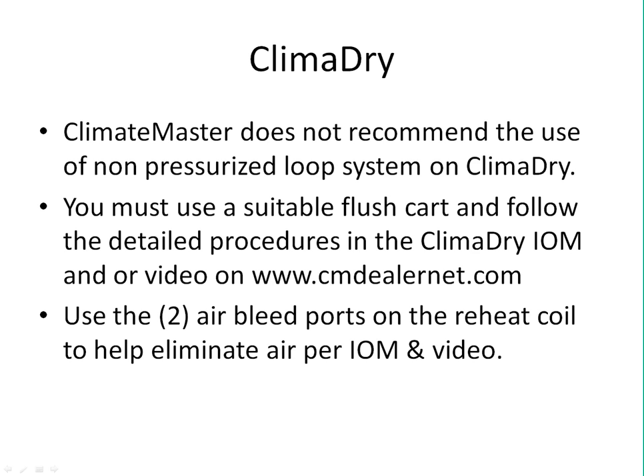With that being said, I also want to state here that ClimateMaster does not recommend the use of non-pressurized loop systems on ClimaDry. We have seen that to be an issue on a number of projects. We don't see it as a very good fit. Again, only on the ClimaDry. Beyond that, if you want to use non-pressurized, that's certainly a choice you can make, but just not on that ClimaDry. We've seen too many issues with it. You must use a suitable flush cart and follow the detailed procedures in the ClimaDry IOM and or the video at that website we referenced earlier, and follow those procedures to make sure that you take the steps necessary to void the air out of that reheat coil.